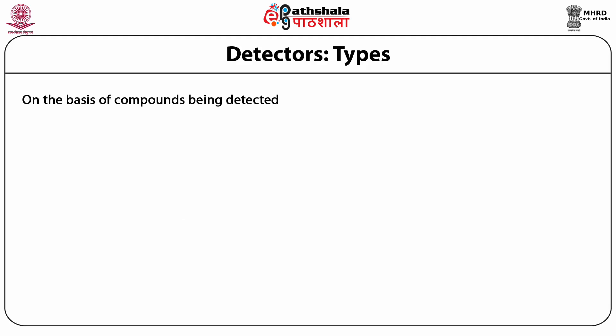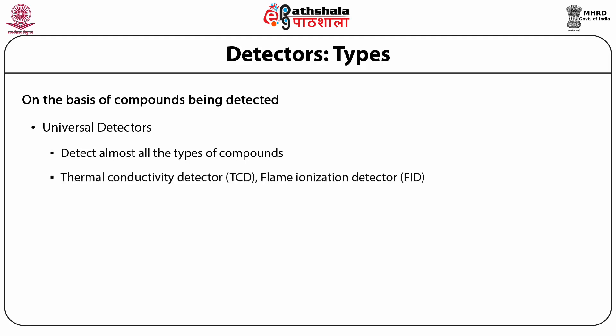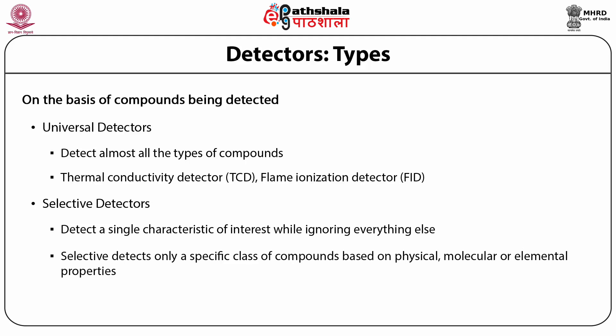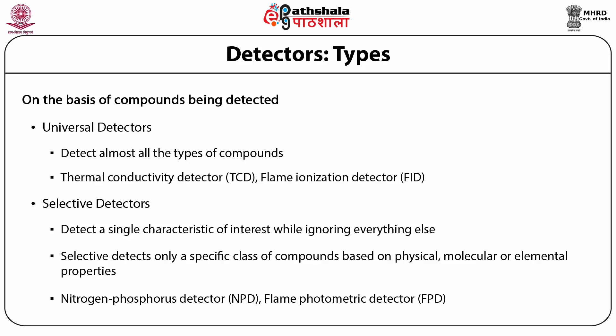On the basis of compounds being detected, gas chromatography detectors can be of two types: universal and selective. As the name suggests, a universal detector can detect almost all types of compounds that elute out in the process — for example, thermal conductivity detector and flame ionization detector. Selective detectors are able to detect a single characteristic of interest while ignoring everything else; they detect only a specific class of compounds based on physical, molecular or elemental properties. Examples are nitrogen phosphorus detector and flame photometric detector.